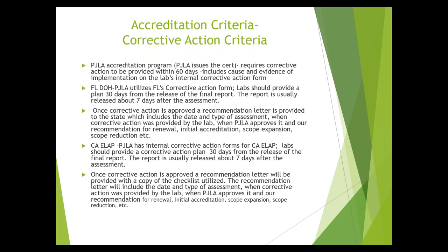Corrective action criteria is handled differently depending on whether PJLA is the accreditation body or a third-party assessor. For programs where PJLA issues the certificate — DOD, DOE, TNI EL, and ISO 17025 — laboratories must provide corrective action including a root cause, implementation, and objective evidence within 60 days from the last day of the assessment. For Florida DOH and California ELAP, as third-party assessors, their criteria and timelines are different.